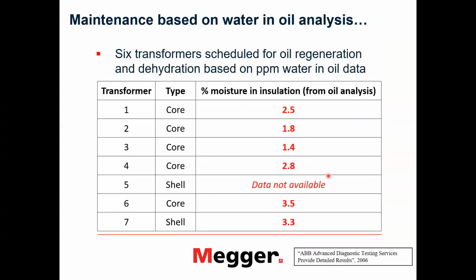Okay, this is also one of the tables, an example of maybe not really correct assessment of transformer conditions based on water in oil analysis. Like I mentioned, it tends to overestimate the moisture content in oil. And here were six transformers which were scheduled for oil regeneration and dehydration, since the water in oil data showed that there is high moisture in insulation.